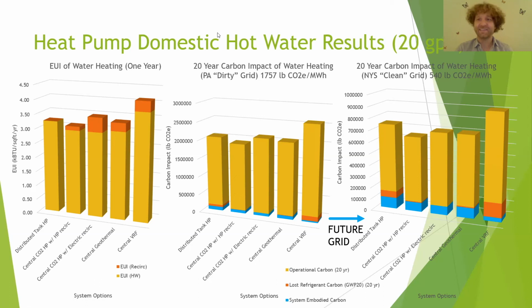I don't want to discourage you from using any of these, but you can see the carbon impacts with the current grid are tracking along with the operational energy, just like they did in all the others. There's very little variance in all of them. Depending on how cold your climate is, that will affect these a little bit more. The colder you get, the more energy you're going to use for all the different systems, but certain ones will do better than others in colder climates. When you get to a cleaner grid, these systems are all really evenly good. So they're all doing well in refrigerant and in operational energy. You can't really go wrong with heat pump hot water.